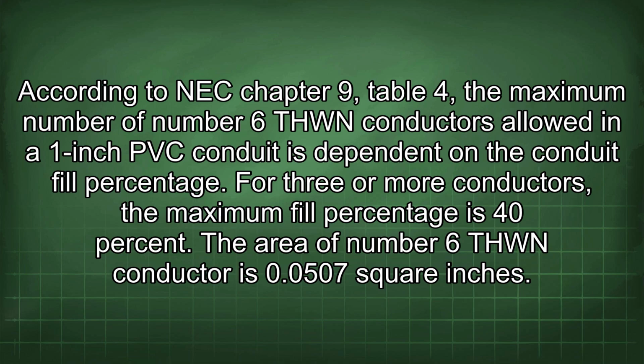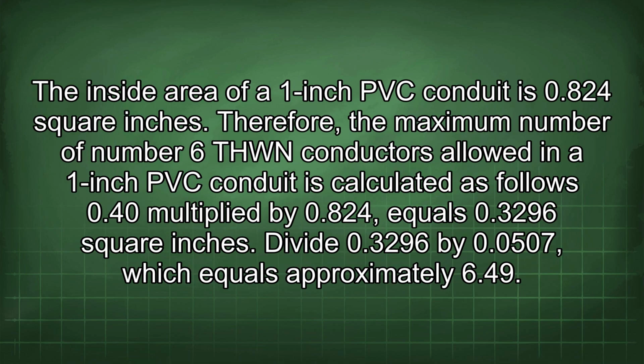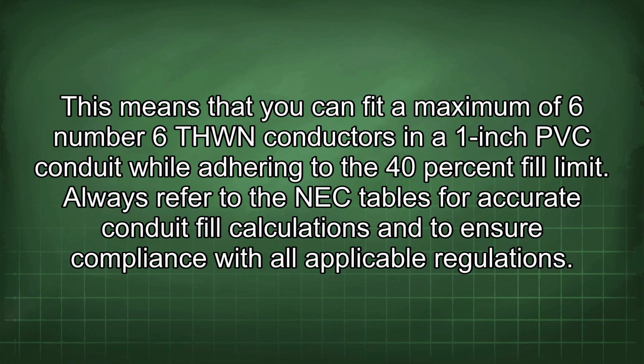The area of number 6 THWN conductor is 0.0507 square inches. The inside area of a 1-inch PVC conduit is 0.824 square inches. Therefore, the maximum number of number 6 THWN conductors allowed in a 1-inch PVC conduit is calculated as follows: 0.40 multiplied by 0.824 equals 0.3296 square inches. Divide 0.3296 by 0.0507, which equals approximately 6.49. This means that you can fit a maximum of 6 number 6 THWN conductors in a 1-inch PVC conduit while adhering to the 40% fill limit. Always refer to the NEC tables for accurate conduit fill calculations and to ensure compliance with all applicable regulations.